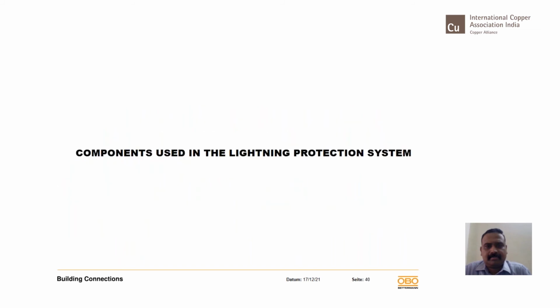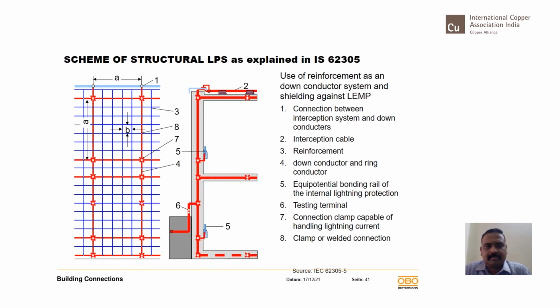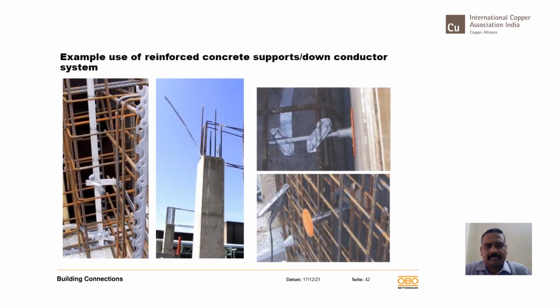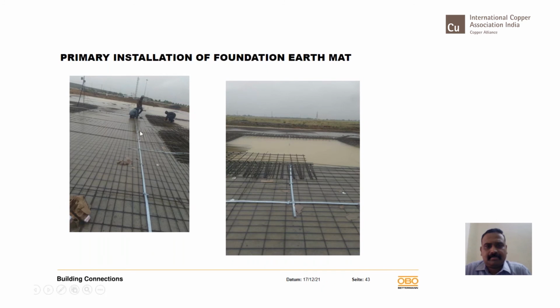Now, there is also a method called a structural lightning protection system, which is nothing other than structurally routing the conductor. In a normal conventional system for an existing building, you will have the conductors routed outside. Whereas in this system, you utilize the reinforcement bars as a common earthing, take the conductors through the reinforcement inside and connect them to the lightning protection system on the top. I'll take you through pictures of a typical installation. You will first lay the rebars. At the rebar level, you will lay the conductors.